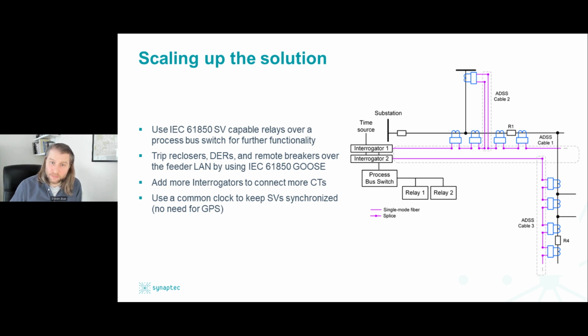Some of the critical functions can be implemented on board the interrogator device. It's a real-time platform which is designed for that purpose. But also all of the measurement data can be delivered to other devices in standard formats, so this can be integrated into wider solutions if needed. The idea here is we're trying to make it as flexible as possible and future-proof. And as Neil explained already, multiple interrogators can work together with coherent time sync of measurements to further expand the coverage for particularly complex circuits with DER, T-points, and other things going on that add to the complexity.